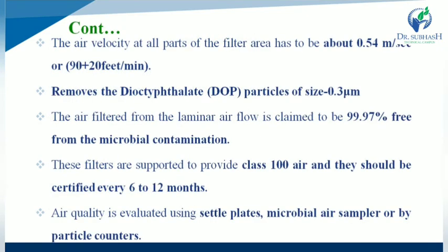So the air velocity at all parts of the filter area has to be about 0.54 meter per second or 90 plus or minus 20 feet per minute. So that is regarding air velocity. HEPA filters remove DOP particles, dioctylphthalate particles, of size about 0.3 micrometer.